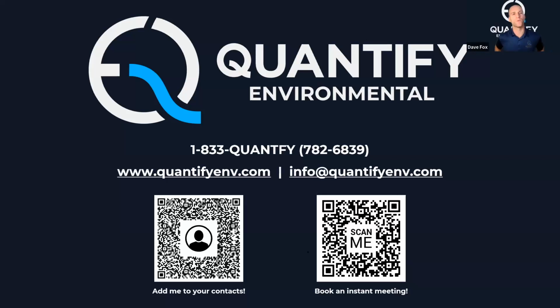To add to that - when we're in facilities looking at existing equipment, even things like 30-year-old boilers, they'll have 4 to 20 output, sometimes Modbus, sometimes pulse. They were put there for a reason - you would have had old SCADA systems tapping into them. With this newer technology, within a few hours we can have systems in place pulling that data, which in some cases the client didn't even know existed.